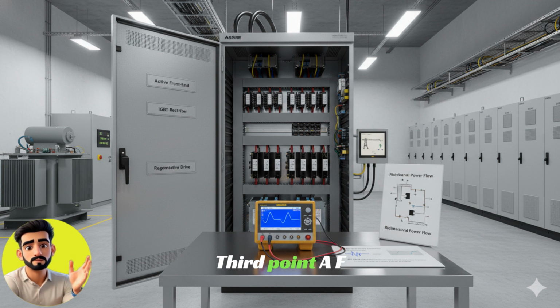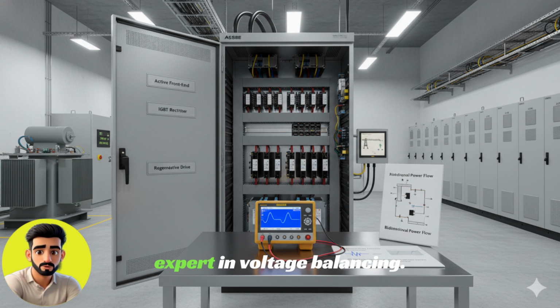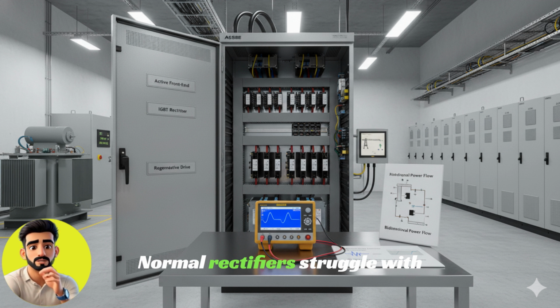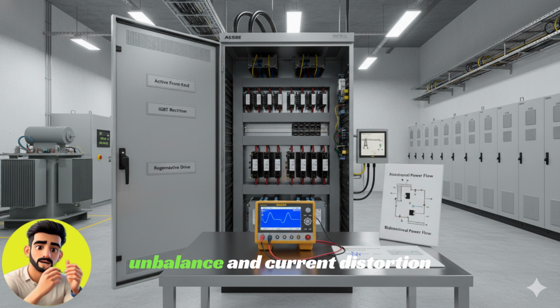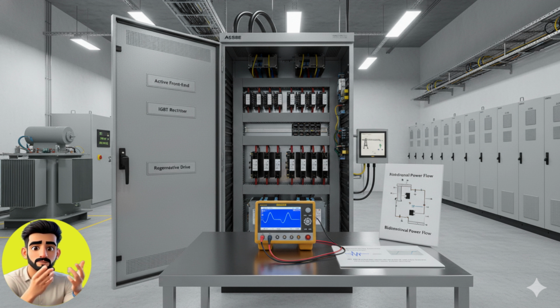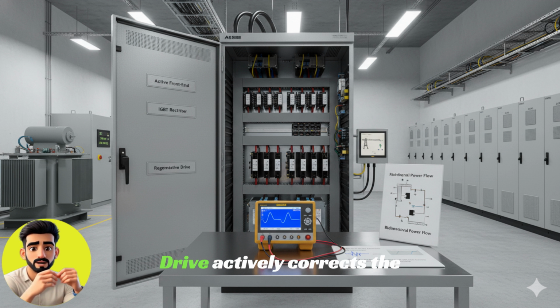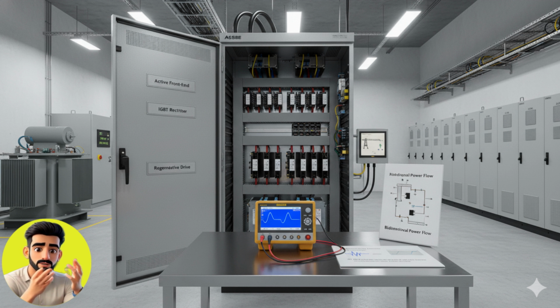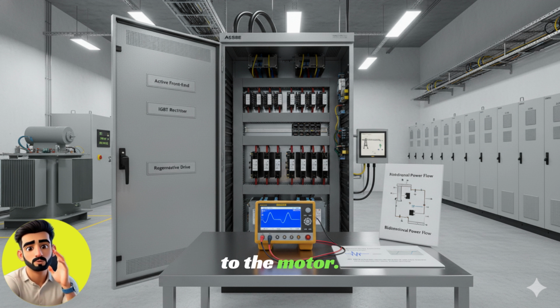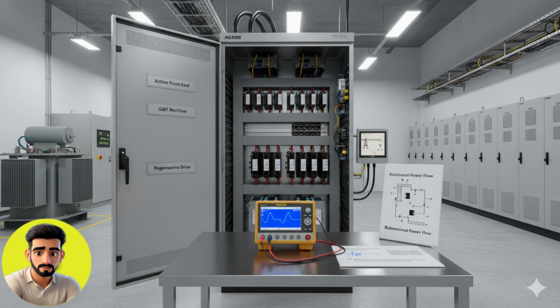Third point. AFE drive is an expert in voltage balancing. Many plants face voltage unbalance. Normal rectifiers struggle with unbalance and current distortion increases. But AFE drive actively corrects the input voltage. It provides a stable and healthy voltage supply to the motor. This reduces the motor's heating and extends the system's lifespan.